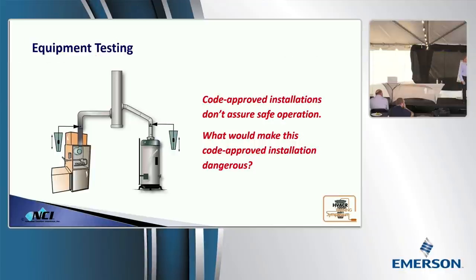What happens if somebody blocks the top of that flue off and the furnace runs? Uh-oh. Remember that a draft hood's definition is also a relief opening. That draft hood will act as a relief opening for that furnace. The furnace will run nonstop and spill 100% of its gases out the top of the water heater. It'll run all day long.